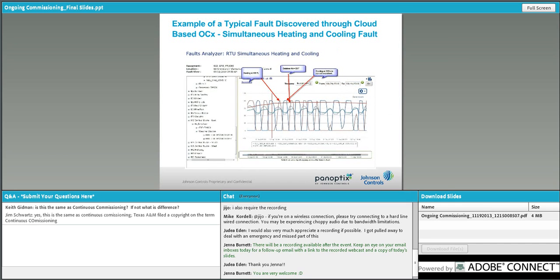So the next few slides just show some example shots of FDD screen captures. This is an example of a typical fault on an air handling unit where the heating valve is at 100%. This is a preheat valve, and you can see the outside air temperature is 90 degrees. Obviously, when the outside air temperature is 90 degrees, the preheat does not have to be on. So this is causing heating up and then overcooling, just a total waste of energy.